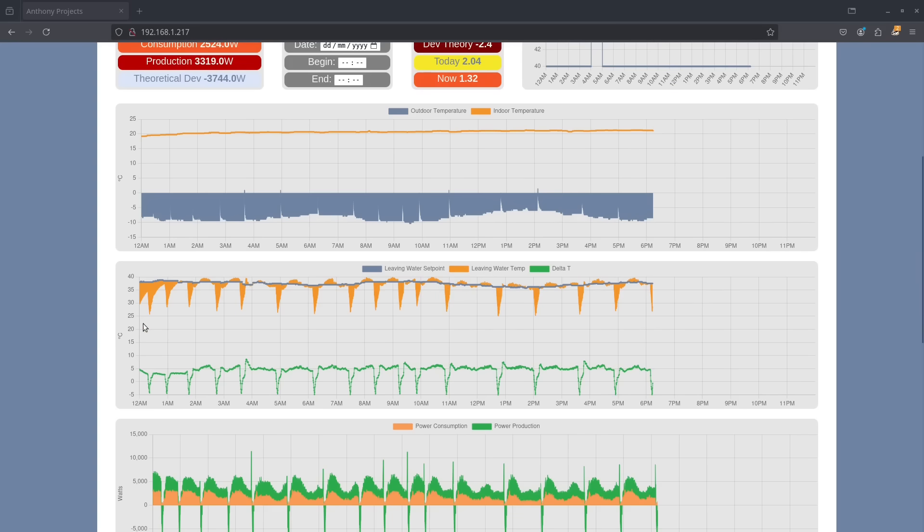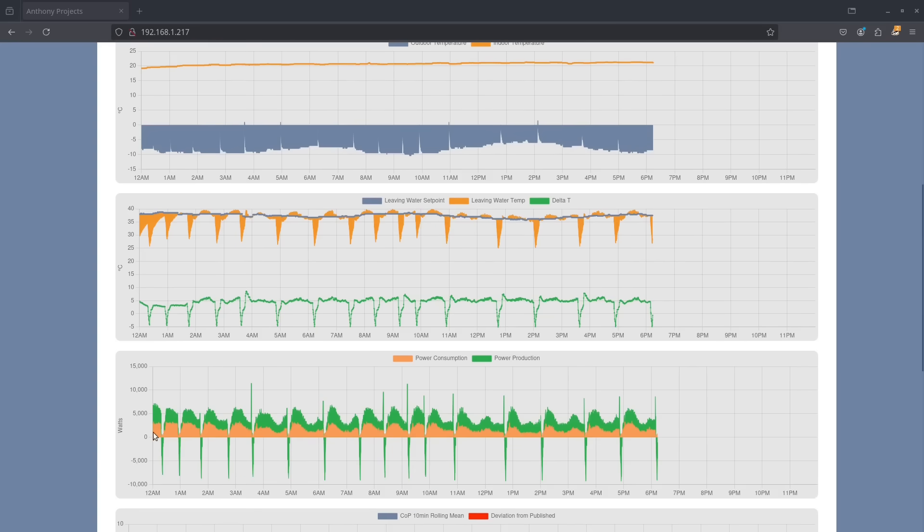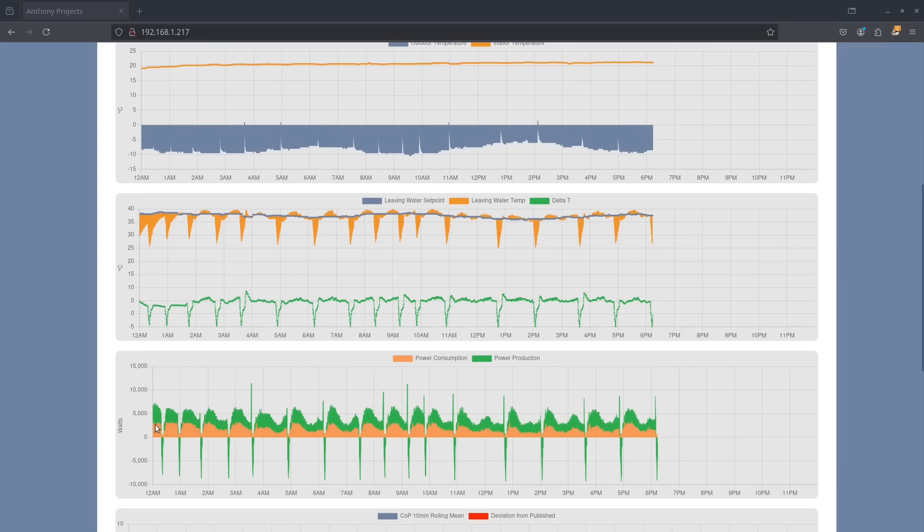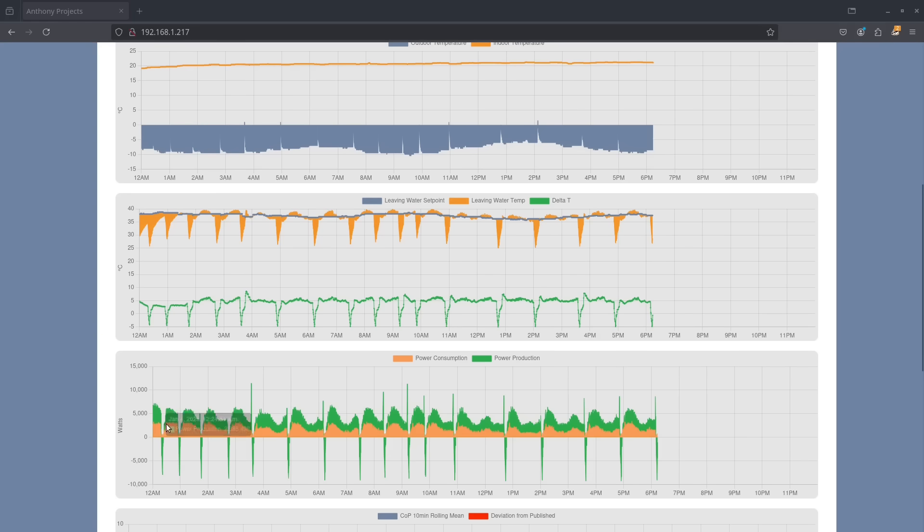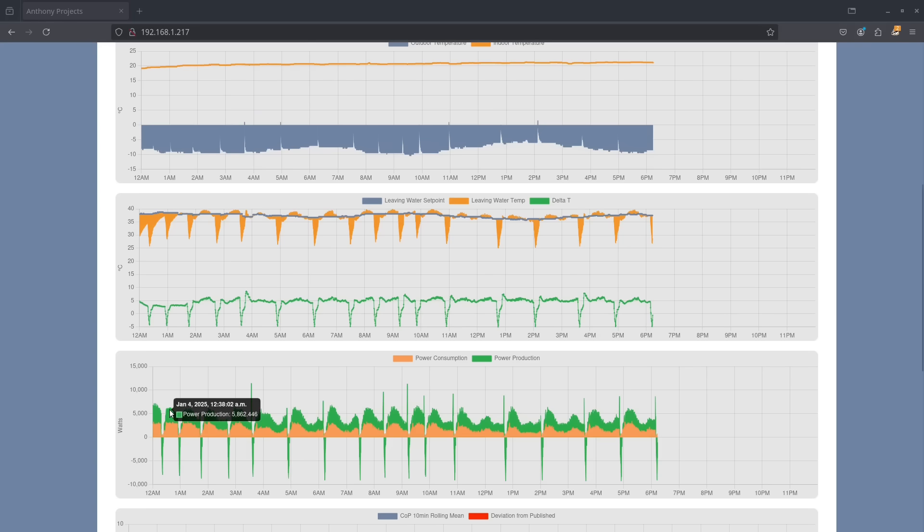All told, you can see that when it comes to bringing the temperature up we have a heat pump output which is about 2.8 kilowatts in terms of consumption and that relates to an actual power production of about 5.8 kilowatts.